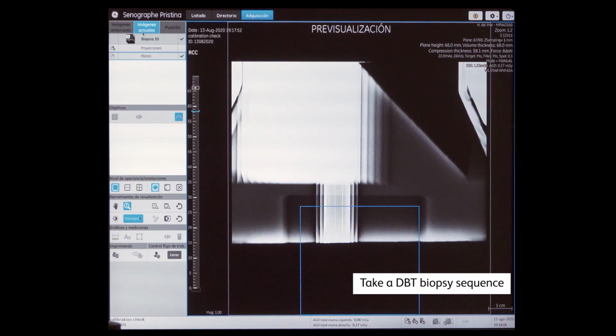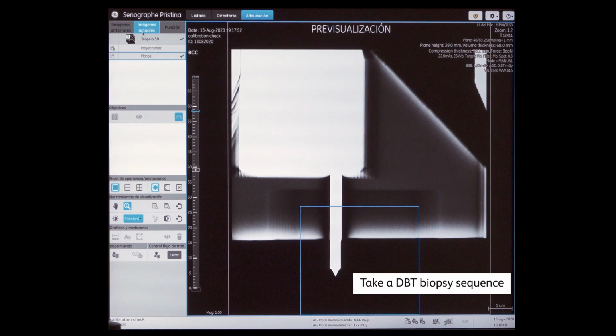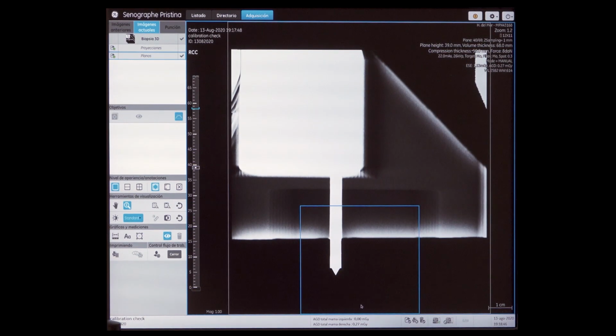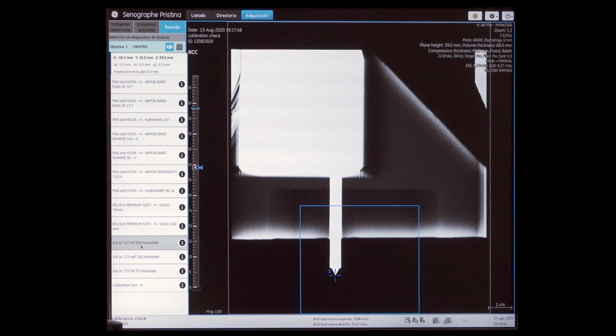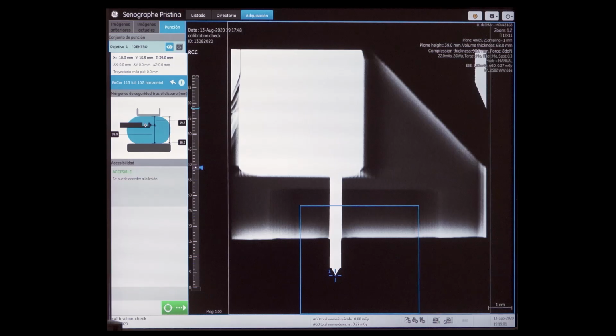Scroll through the images and select the plane where the calibration needle width is greater and the tip is well defined. It should be close to the 40 mm plane. Place the marker in the target. Select the EnCor 113 full 10G horizontal needle. Check accessibility and send the coordinates.